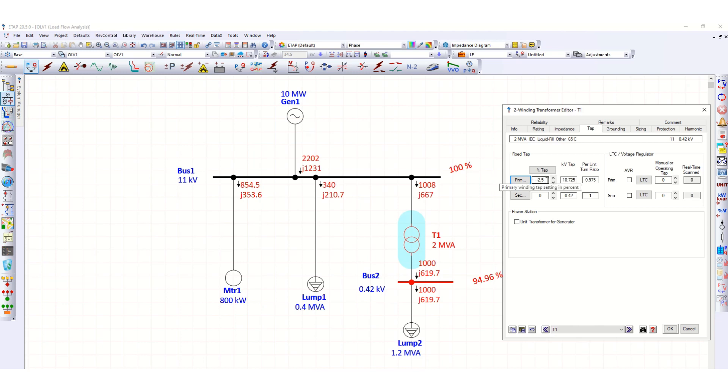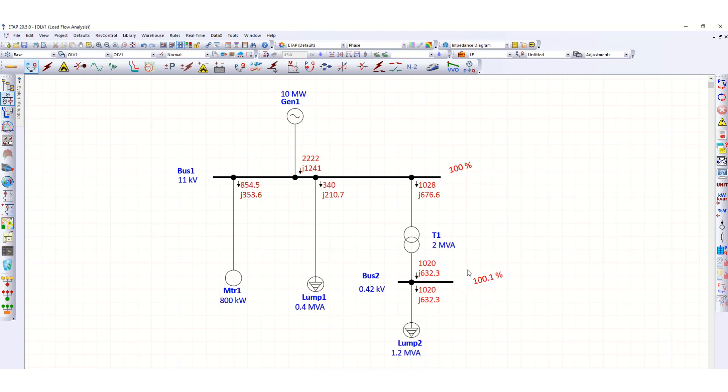Now click OK. Let's run the load flow analysis again. Now you can see this voltage profile is improved, this voltage profile of this bus is improved. So at 0% transformer tap it was 97.45 percent, and now it is improved to 100.1 percent.